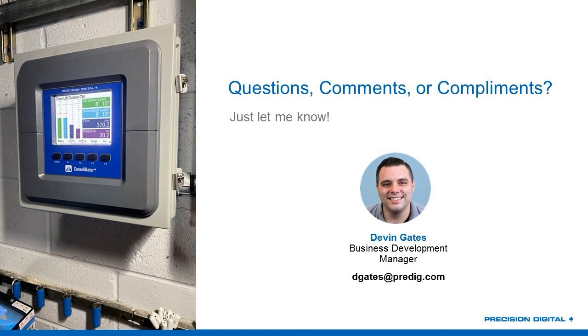Somebody asked, for the averaging, if one of the inputs goes to fault, or the difference is too much, or there's too large of a difference from the rest, can the average be programmed to ignore the fault input from the averaging? Yes. I would have to sit down and figure out exactly how to do it. But just based on other applications I've configured, yes, I can have the ConsoliDator Plus ignore all sorts of different things for all sorts of different reasons.